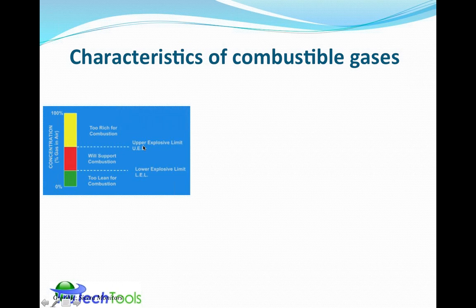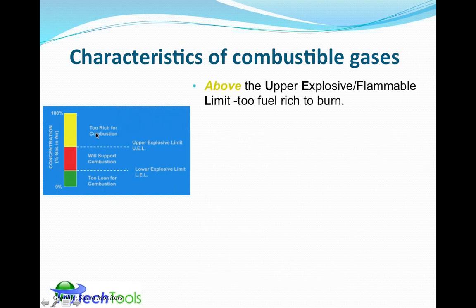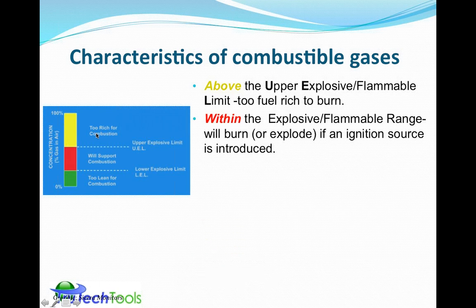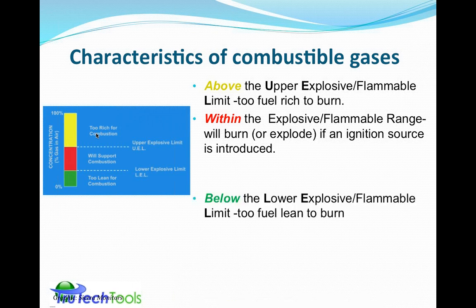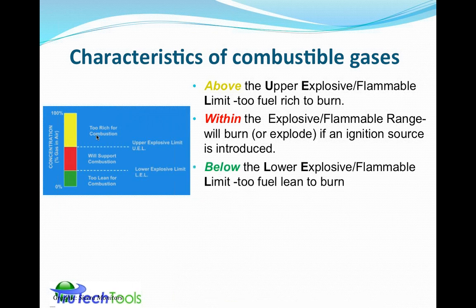Moving up to the upper explosive limit, that's the point where it's too fuel rich. There's too much gas concentration in the air for it to support combustion. So above the upper explosive limit, it's too fuel rich to burn. In the red zone here, it can explode or burn if an ignition source with enough energy is introduced. And here we go back to the enough energy statement. Enough energy comes from the way the device is designed, designed and used to make it intrinsically safe. Below the green area here, below the lower explosive or lower flammable limit, it's too fuel lean. There's not enough fuel to burn.